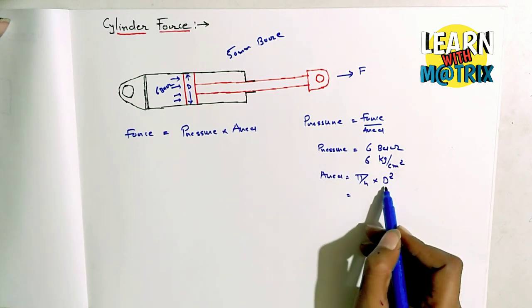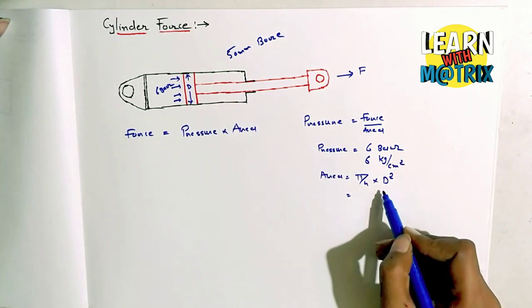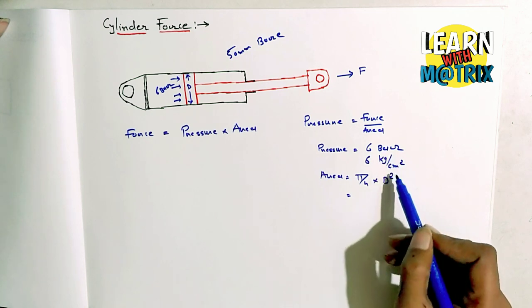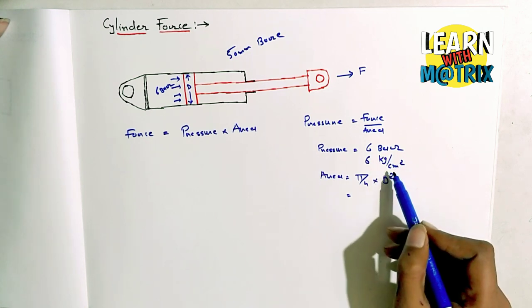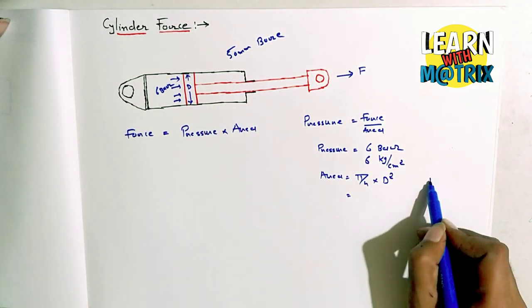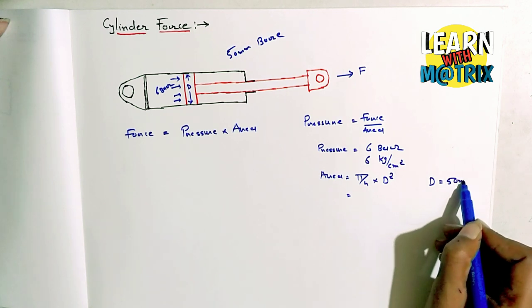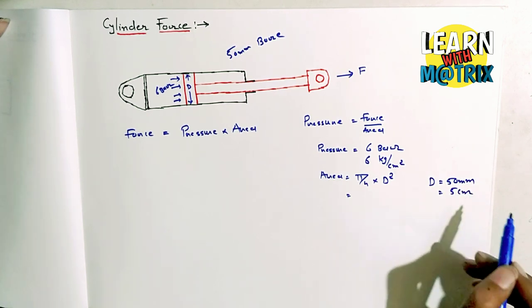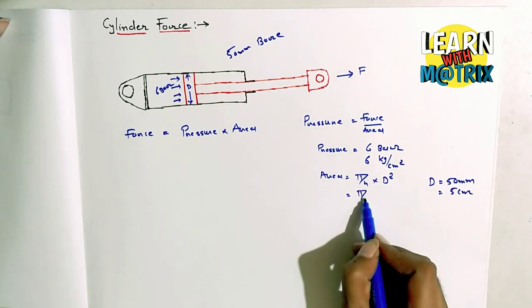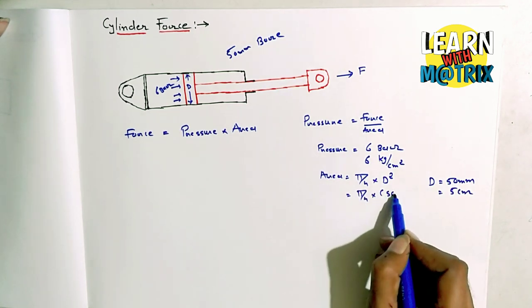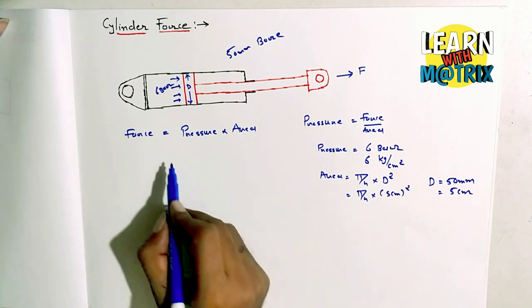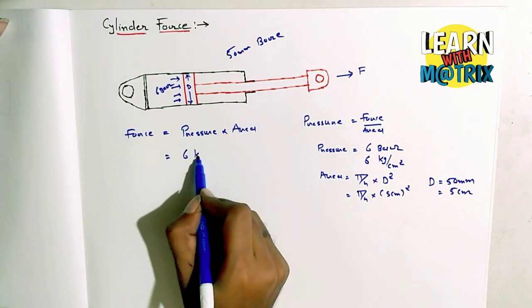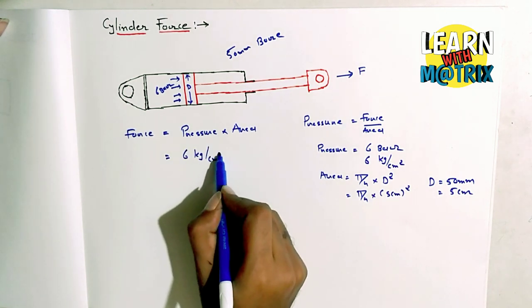So d we know is 50. As you see, friends, bar means in centimeters, so 50 mm we need to convert to centimeter - 5 centimeter.